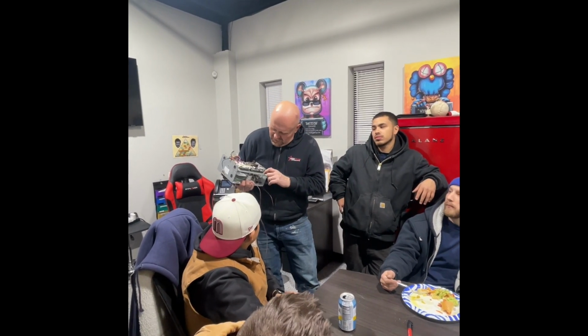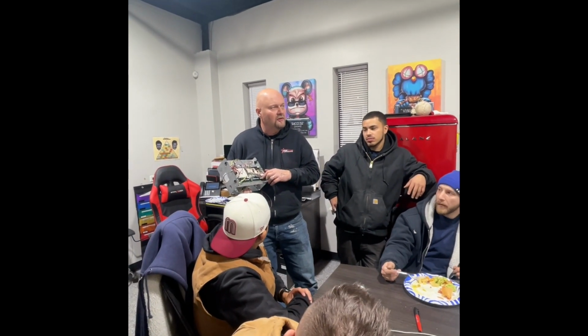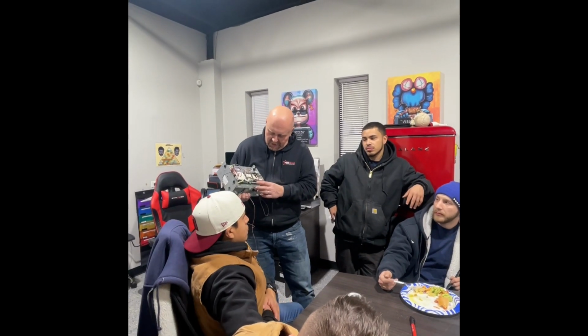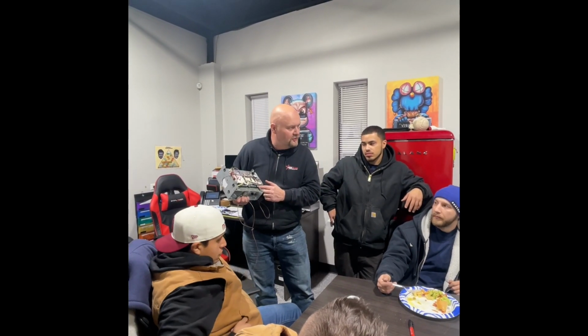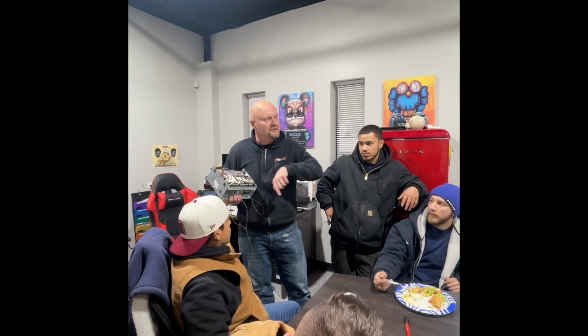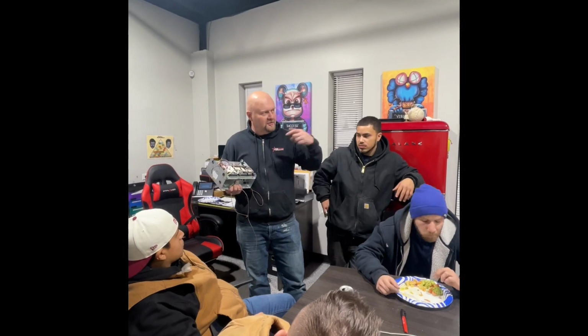So no power given by the control, it just makes that switch for you. So the transformer from the boiler downstairs sends its own R to this hot W here, and when there's a W called here, call for heat, this will close the connection between these two screws and send a W signal back down to the boiler, which will then engage the pump, bring on the heat from the boiler, and allow the hot water to circulate into that coil that we talked about. So that's the third transformer.